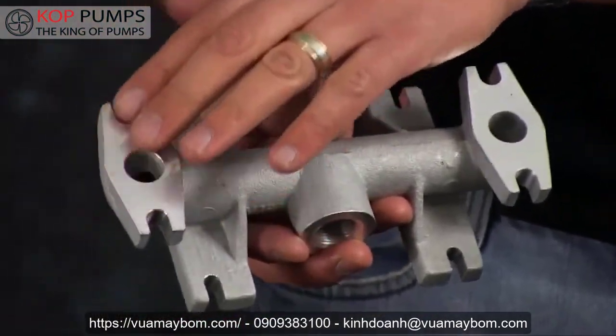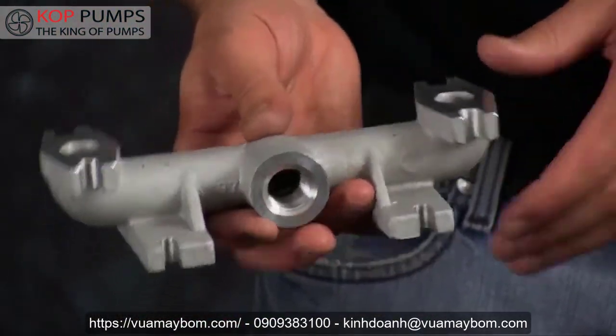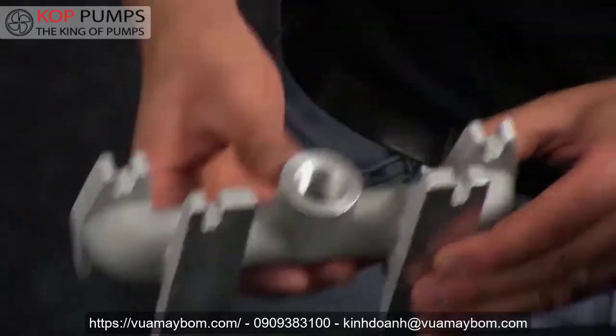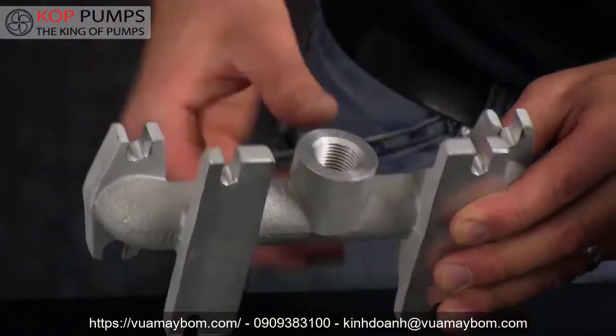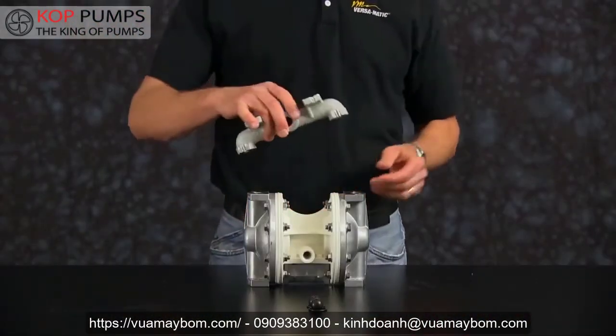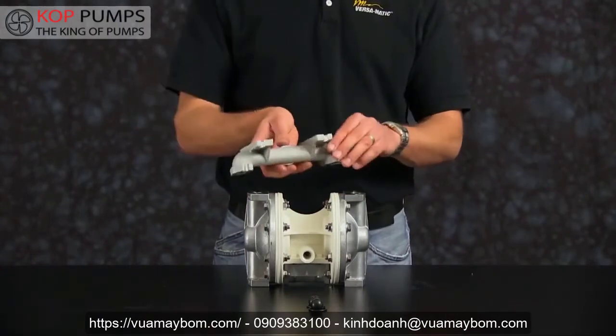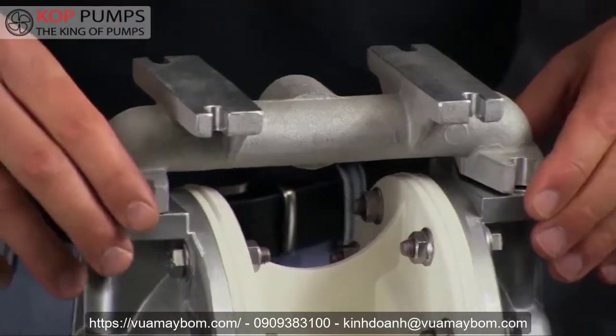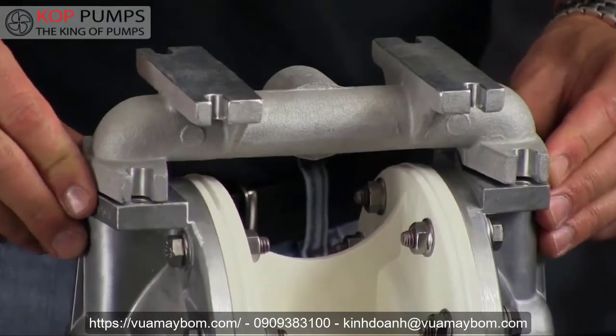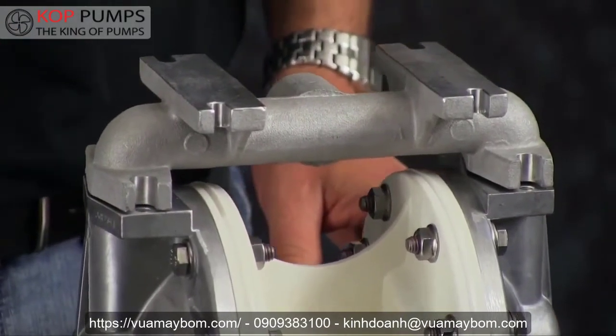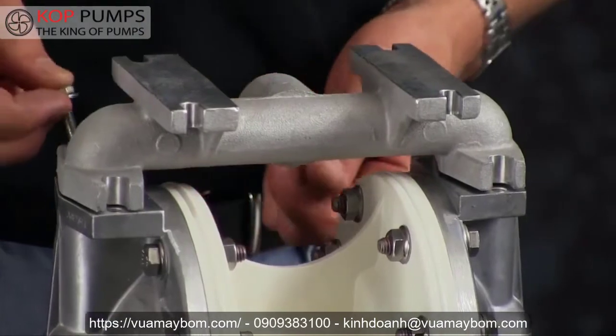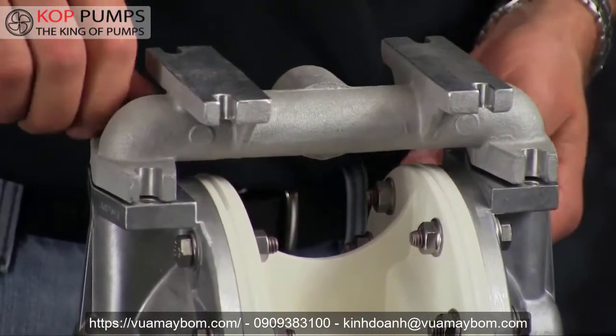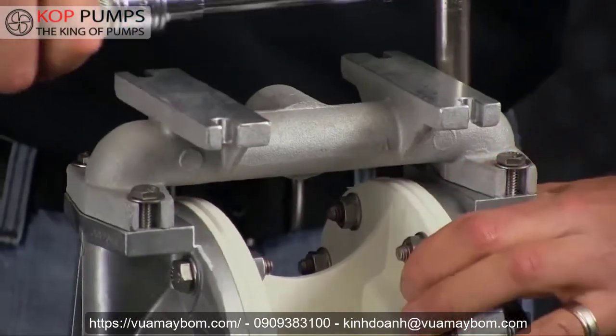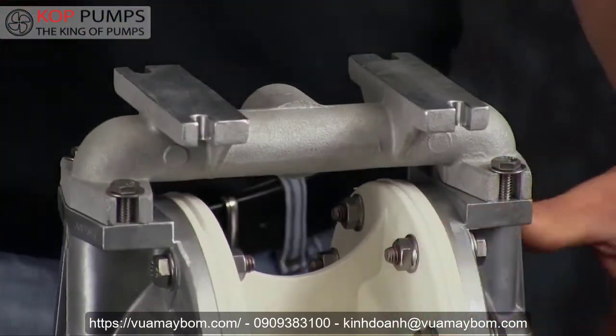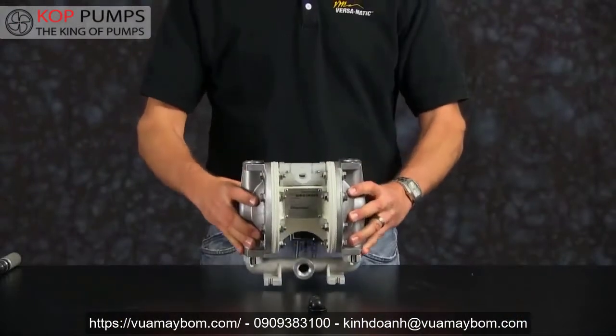We want to inspect the manifold for scarring, damage, or material buildup. Check the casting for wear. Check the port for thread integrity. Repair or replace as needed. Orientation of the manifold is based on process requirements and may be reinstalled in either direction. Torque the suction manifold bolts in a cross pattern according to factory specs listed in the service manual.